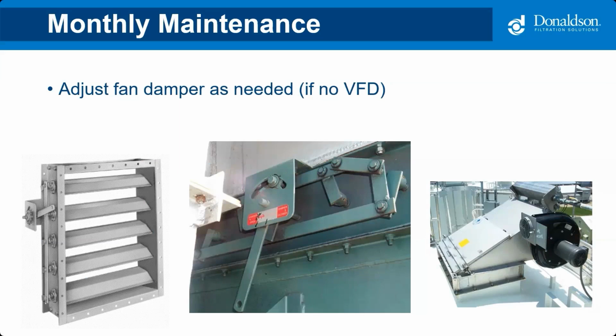If you don't have a VFD on your collector, if it's a simple kind of on-off, just the fan comes on at full speed, it's likely equipped with a damper. And so what the damper does is it creates restriction. So when you put a new set of filters in, you want to adjust the damper down to create additional restriction so your flow is proper in the ductwork. Then as the filters load, you have to open that damper back up because now the filters are creating the adequate restriction for the flow.